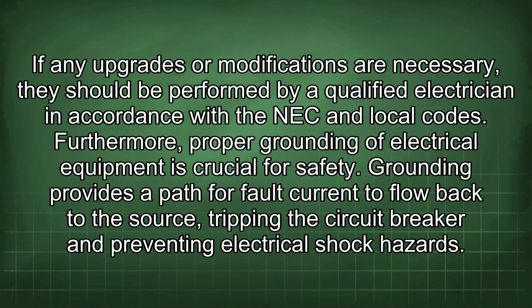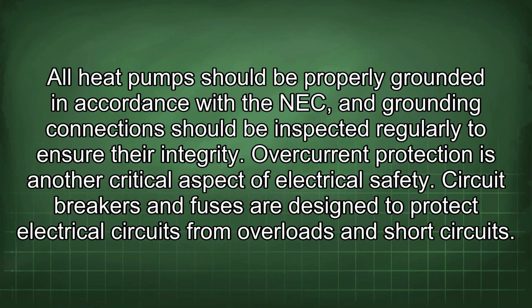Furthermore, proper grounding of electrical equipment is crucial for safety. Grounding provides a path for fault current to flow back to the source, tripping the circuit breaker and preventing electrical shock hazards. All heat pumps should be properly grounded in accordance with the NEC, and grounding connections should be inspected regularly to ensure their integrity.